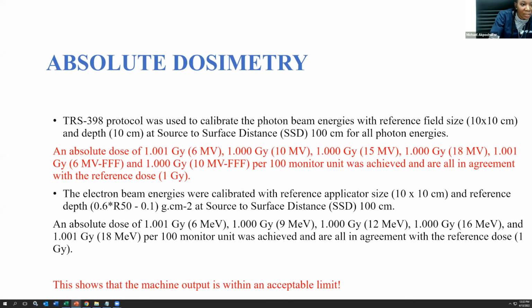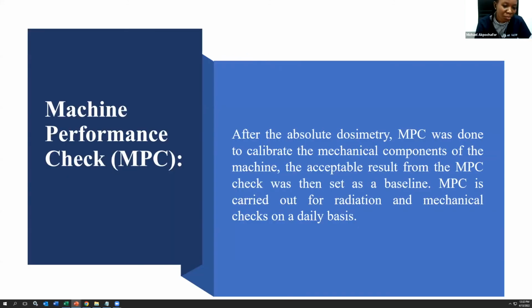Now, after this, we go on to MPC. This absolute dosimetry is what we use to set the baseline. We tune the machine to set the baseline, looking at all the results that we get. After this is done, we go on to what we call the machine performance check.